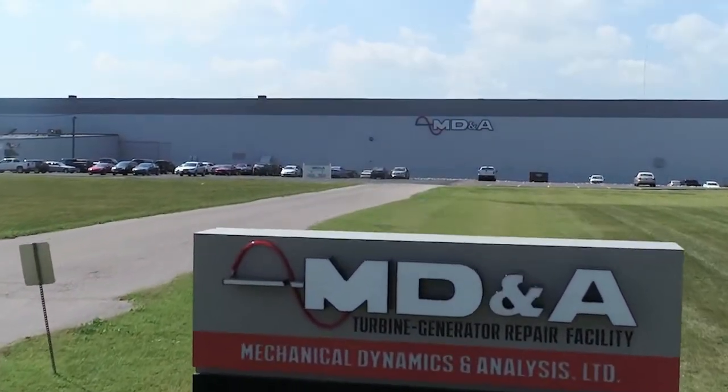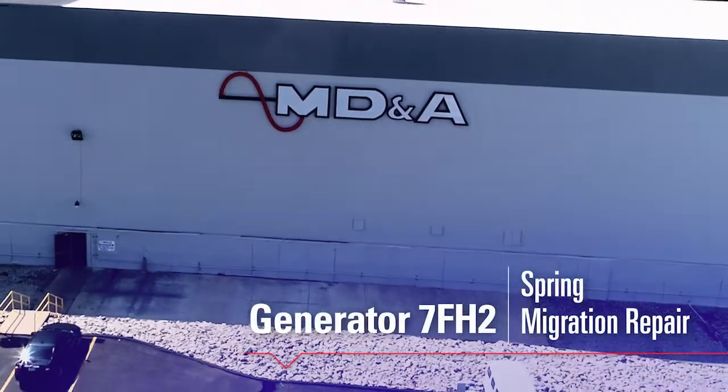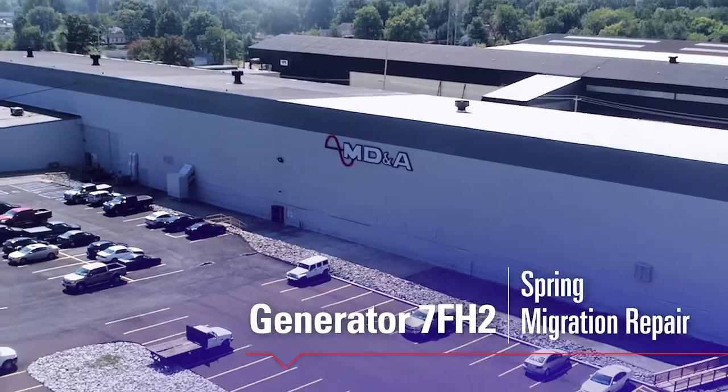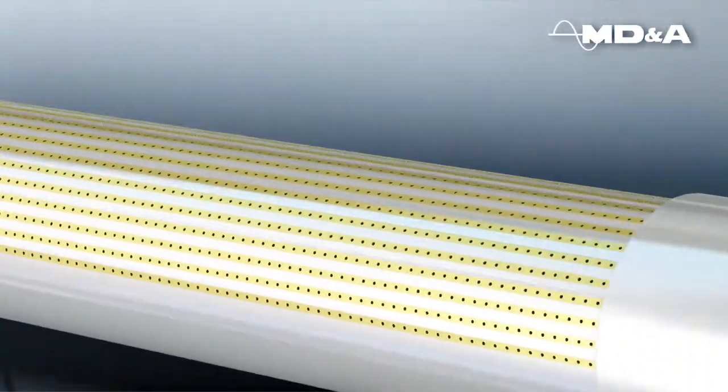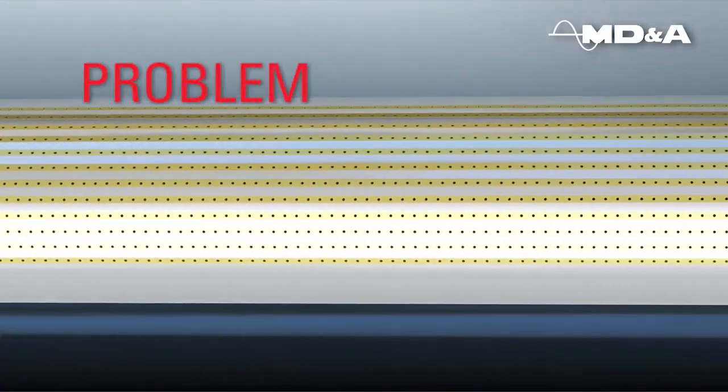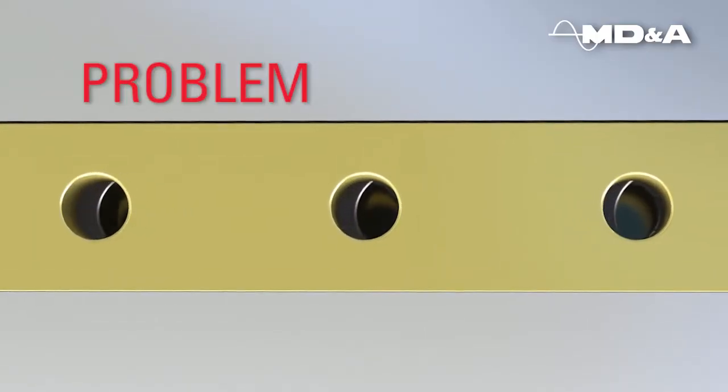MD&A experts offer a unique patented repair process that eliminates 7-FH2 spring migration and restores your generator to full operation. This problem occurs during normal field operation as the springs under the full length of amortiser migrate axially within the slot. The migration of the springs can lead to blockage of the radial ventilation passages.